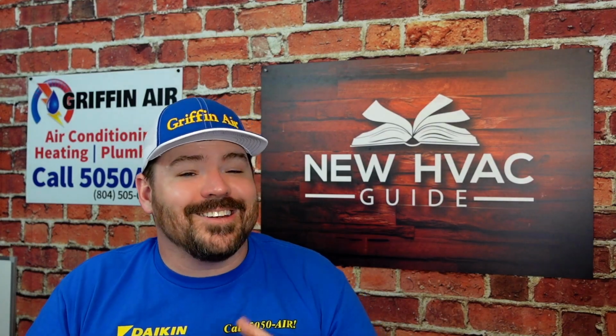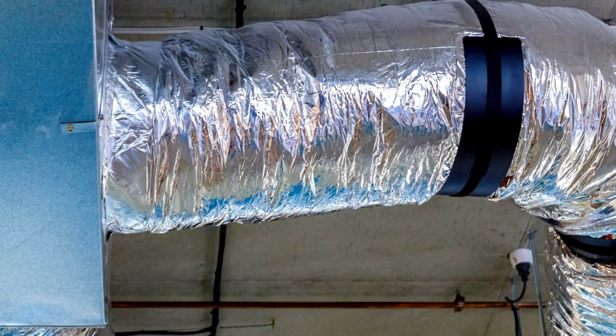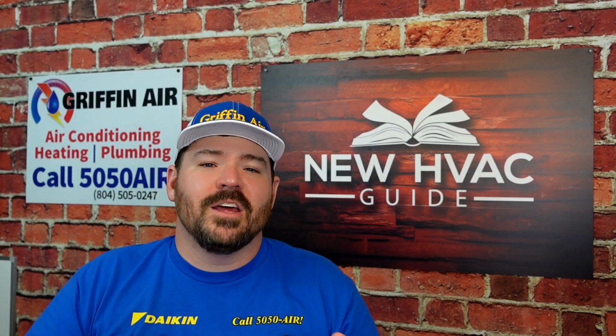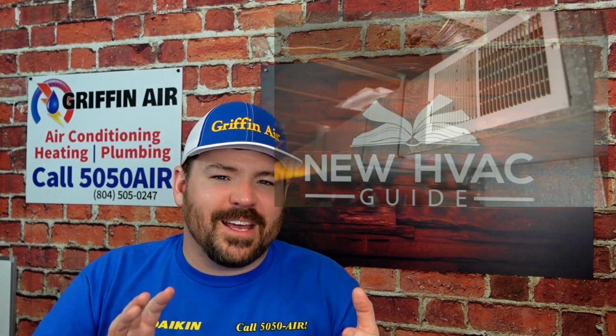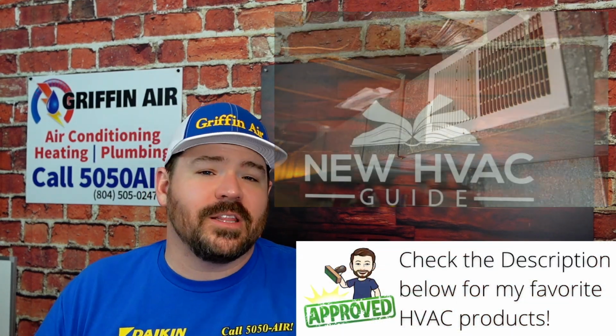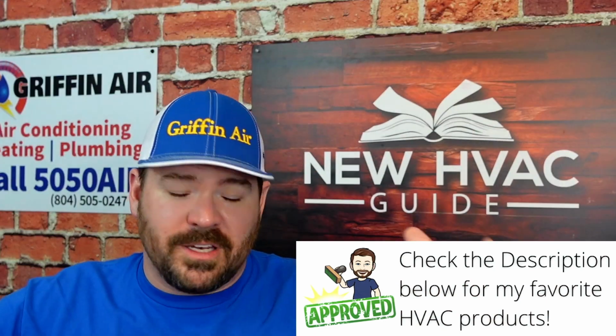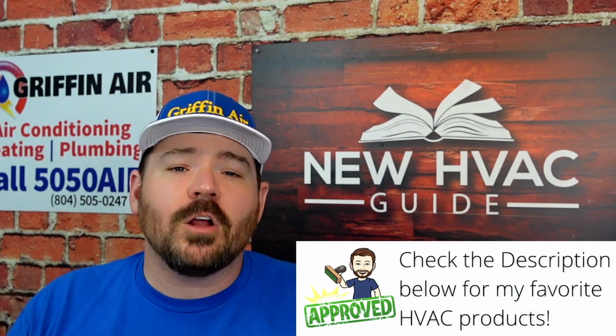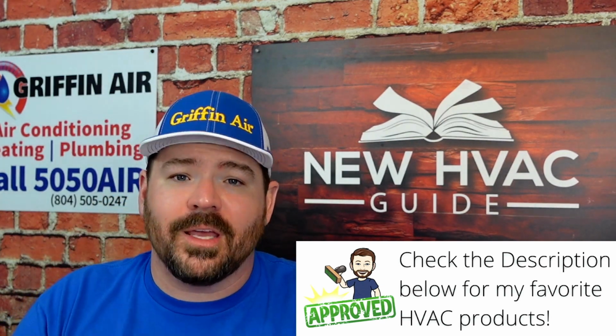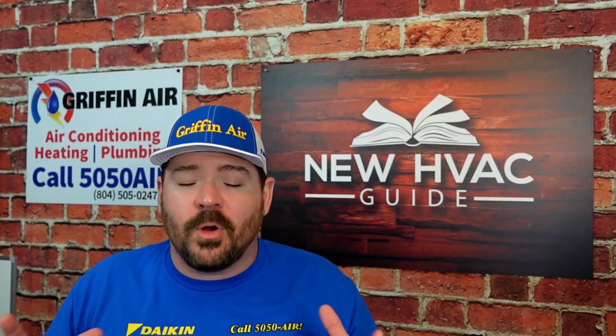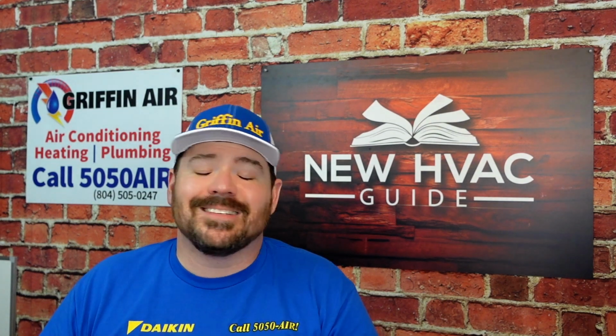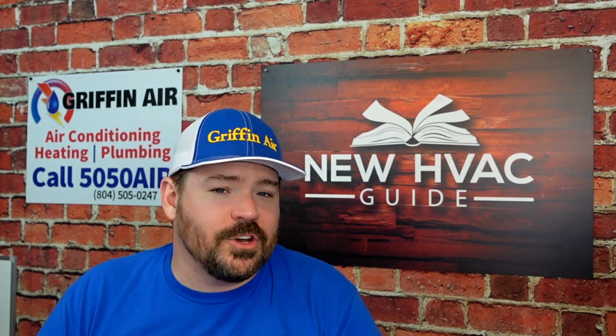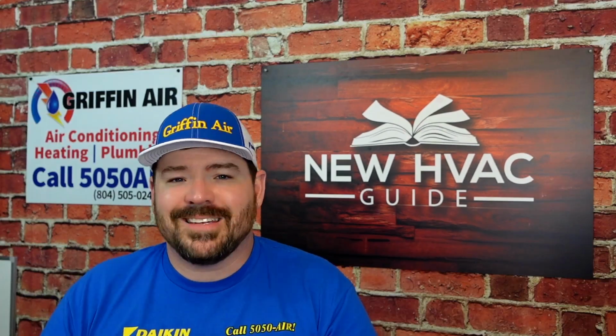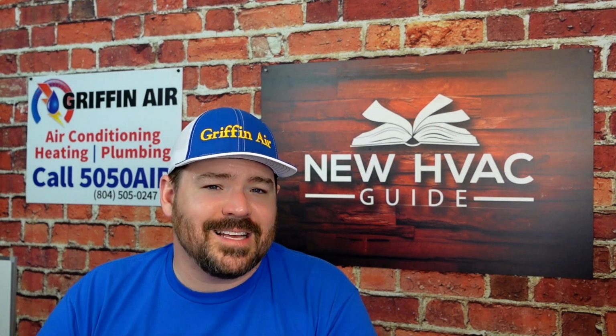Number three, you've got a ductwork issue. Some sort of duct issue can cause vibrations. We've had customers call us and say, not only is it vibrating a little bit, the ductwork itself can almost bang in and out as it's expanding and contracting, depending on whether or not the airflow is being pulled through there. There are different types of ductwork issues that could be causing the vibrating. And sometimes the system itself, it literally does have air being pushed through there. And you've got to have ductwork that's sized properly and installed properly to be able to handle all of that. I can't speak for all parts of the country, but I can tell you that here in Virginia, it's not uncommon for us to see everyday ductwork that's undersized, and you're choking that system for air, literally. Different types of duct issues can cause vibrations, and that's something else you can watch out for.